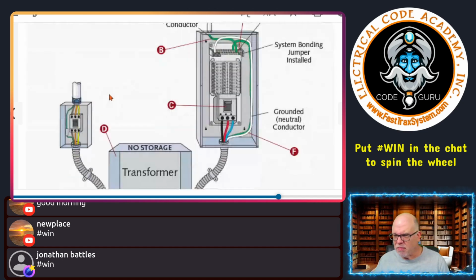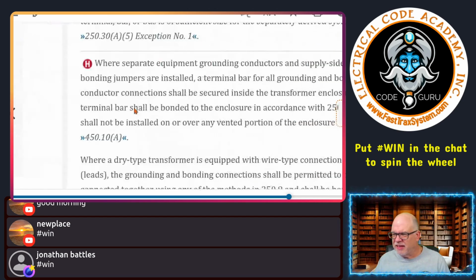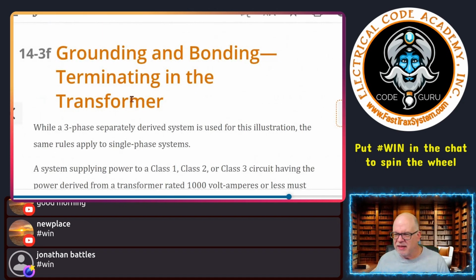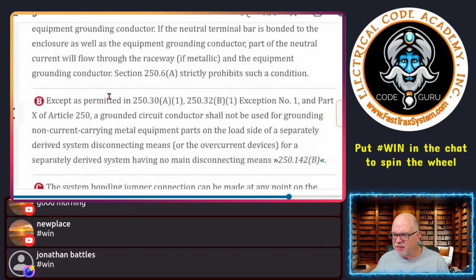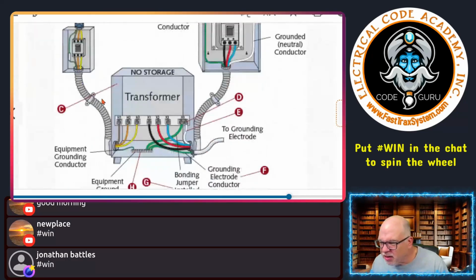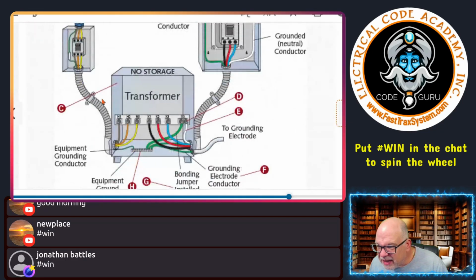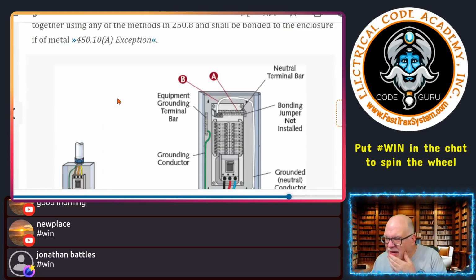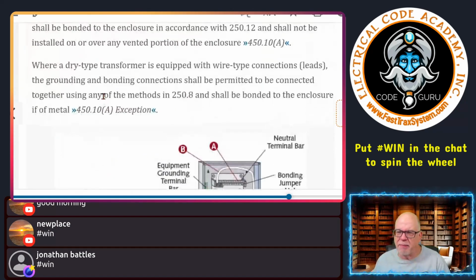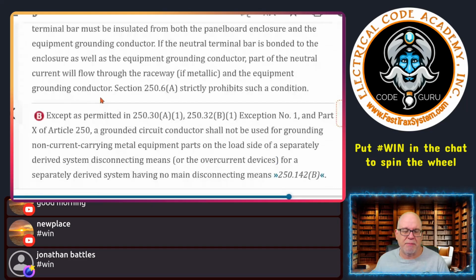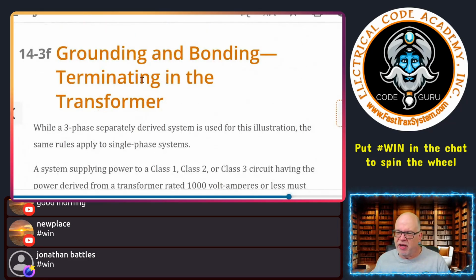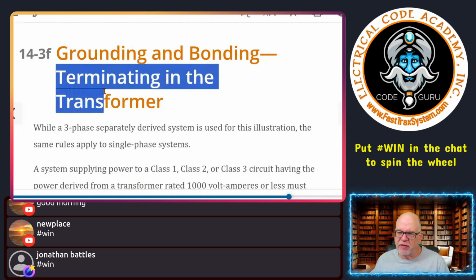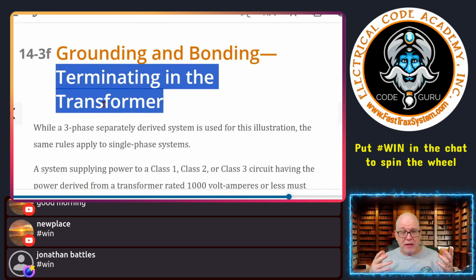Okay. All right. Let's see if there's anything else for the grounding and bonding. Let's see here. Let's see if we got a picture here. Yeah. So that one was one. Let's show you the same example here. I might as well cover both. So here's grounding and bonding terminating in the transformer. So then my most favorite place to do it is in the transformer. And then we separate the conductors in this panel that it supplies, right? That's typically what you're going to do with a transformer.